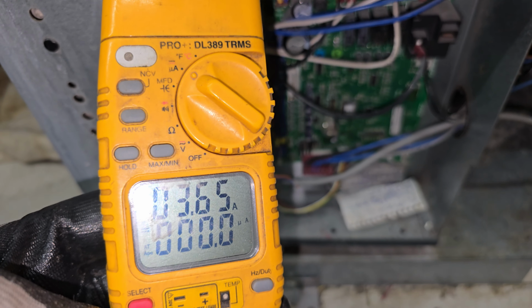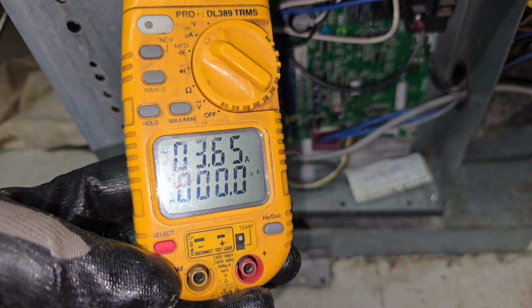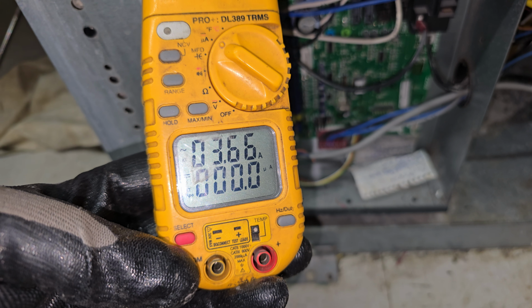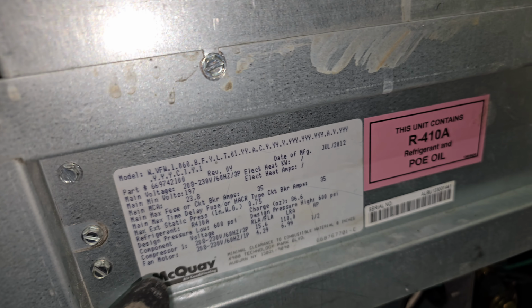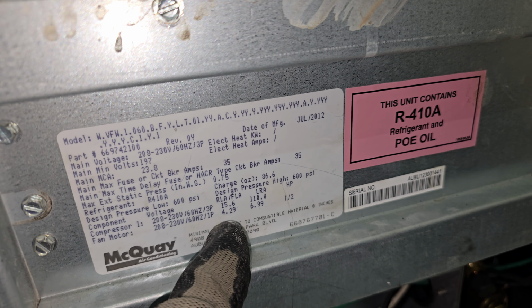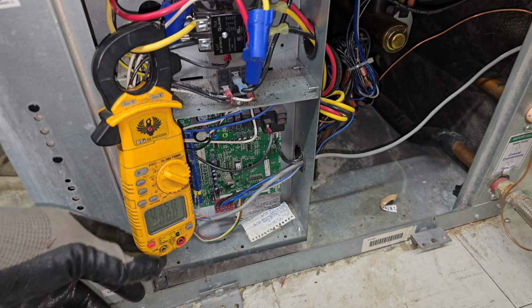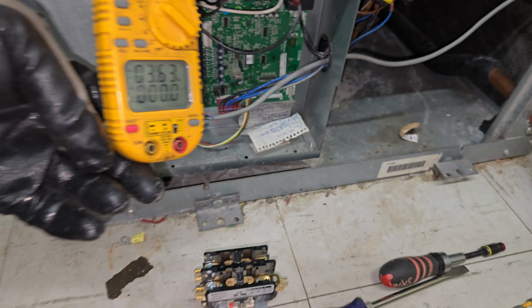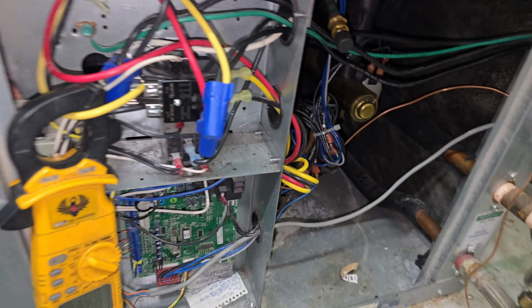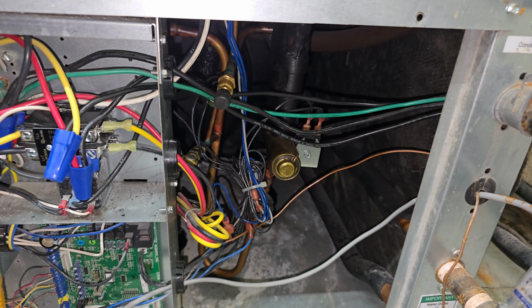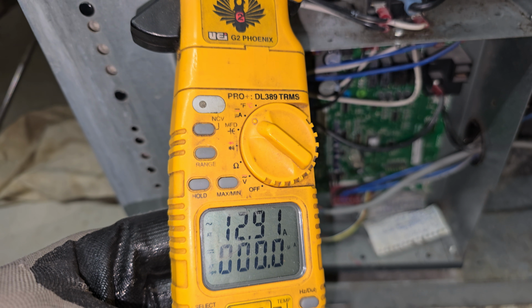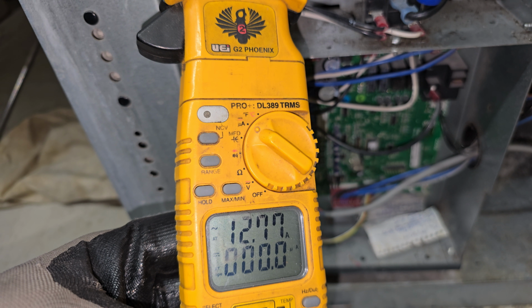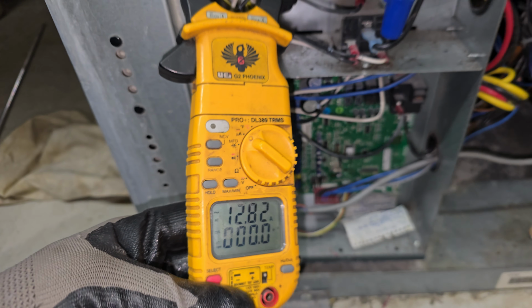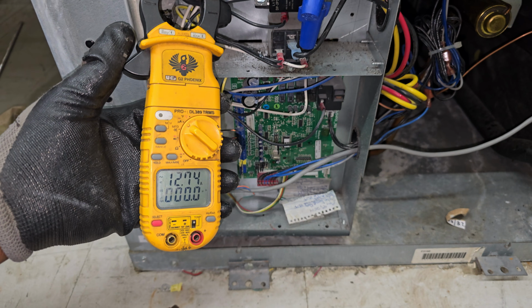Okay, with only the blower motor, you can see my amps reading is 3.66. But here the manufacturer is saying my blower motor is 4.29, which is okay. So I'm getting 3.63 when only the blower motor is coming on. Okay, so we want to see what the compressor amps reading says when the compressor eventually kicks in. Okay, so my compressor kicked in, and here is the amps reading. 12.7, 12.8 amps is what I'm getting, total amps reading.